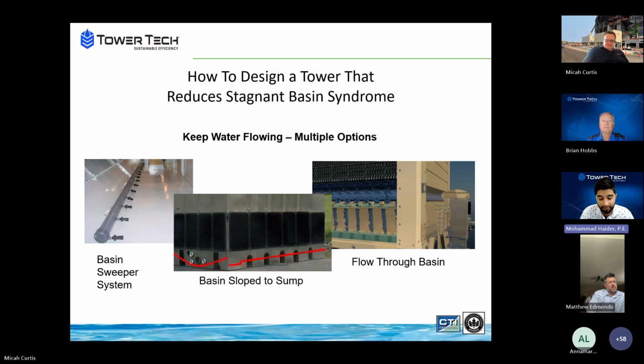And the reason is, as you can see with the basin sweeper design and in my personal experience, you get zones either in and around or underneath the basin sweeper that'll start to accumulate to some high degree sediments and organic particles. And so, yeah, basin sweeper systems are better than nothing, but still, they add another point of concern when it comes to the collection of organic particles that feed Legionella. And really what we're talking about is trying to get rid of stagnant water, right? Yep. And that's back to the root core of the problem of cooling towers.